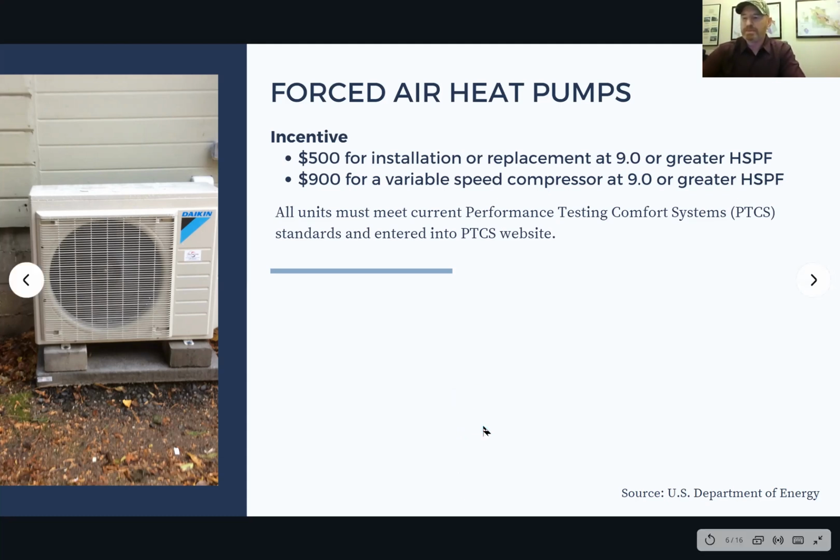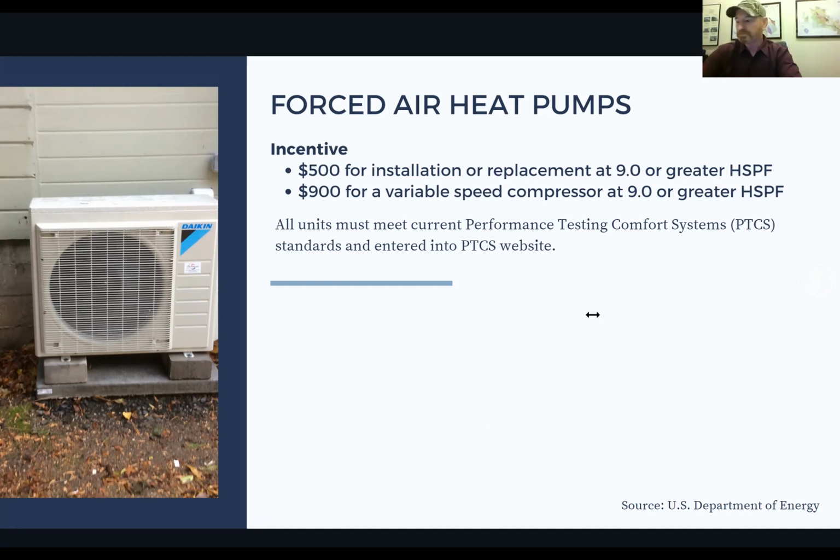With the heat pump, there's some extremely important things to do. You need to worry about the sizing of the unit. Think of how many BTUs the unit can produce, the size of the motor, you may think. And heat pumps, they always talk in tons, which gets confusing to customers because nobody else uses tons. A ton is 12,000 BTUs. So that's part of my audit: I'm doing a heat loss calculation and sizing the unit properly for the home.